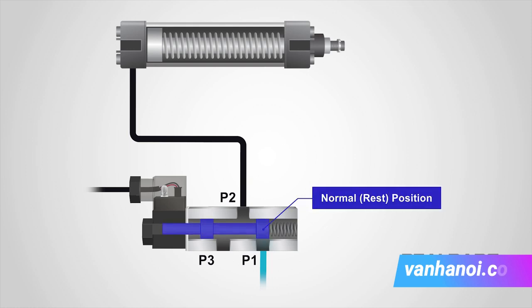In the normal state, without the actuator being operated, nothing will happen, as the spool is physically blocking the airflow at port 1, and the cylinder is retracted because ports 2 and 3 are connected due to the spool position. So any air already within the system would escape to the atmosphere through the exhaust port. Let's consider this the normal or rest position.